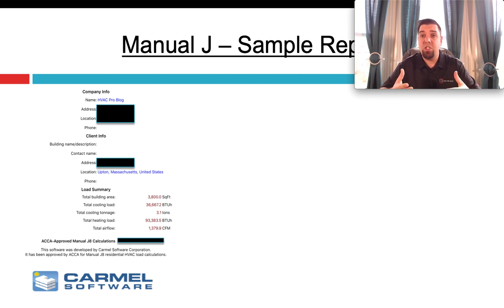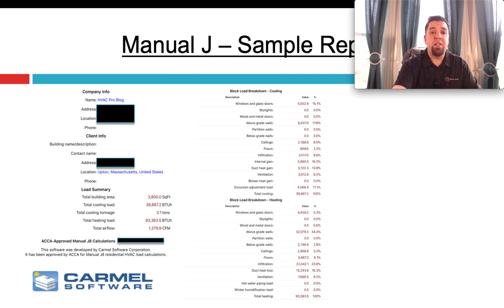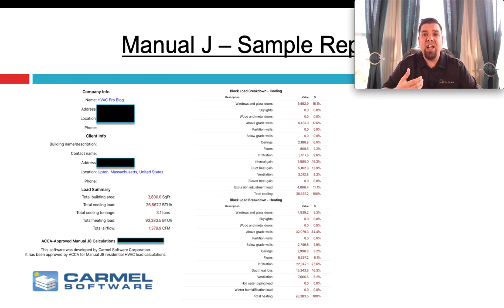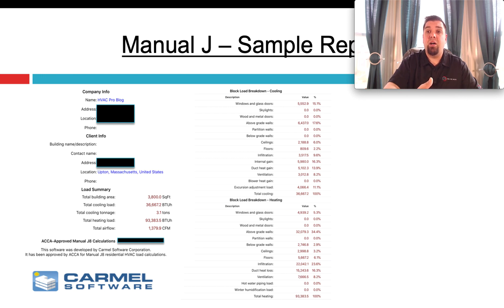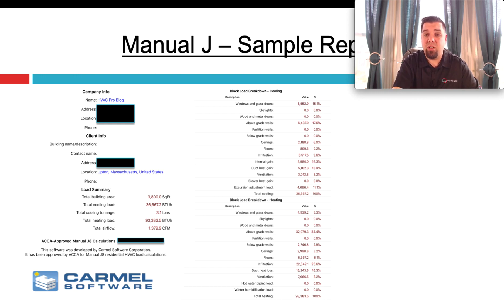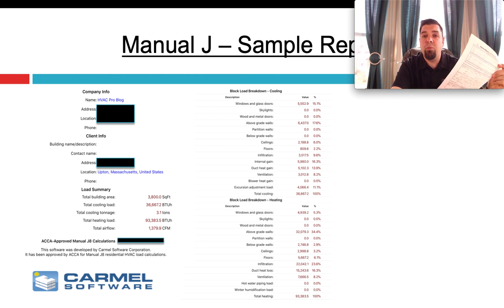Let me show you a couple of reports. This is from Carmel — this is actually my house that we used as the study home. You can see the load calc here, and the information you're looking for is square footage, total cooling load, and total heating load. On the cooling side, you want to break that out into latent and sensible gains — that helps you select the right size piece of equipment, especially on a ducted system. You also want to look at the percentages to make sure you didn't miss anything. For example, if I know I have skylights but the report shows zero, I missed the skylight — a very quick and easy thing to check.